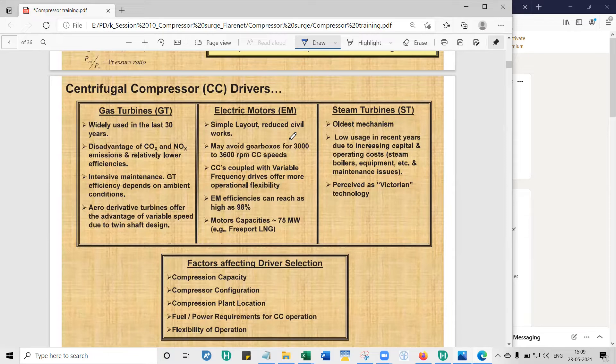Now, the motors that you get are 3,000 or 3,600. That is, you can have a 2, 4, 6 or an 8-pole motor. And you have 50 hertz and 60 hertz current. So the formula is simple. 120 into F by P. So 120, so let's say it's 50 hertz and 4-pole motor. So 120 into 50 by 4 comes to 3,000 RPM. Let's say it is, because U.S. is the only country which uses 60 hertz. So 120 into 60 by 4 gives you 3,600 RPM.